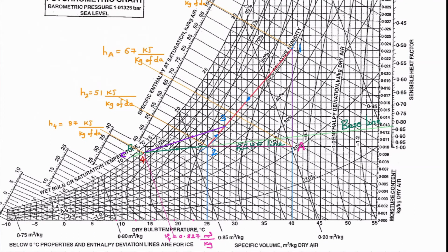Okay, now in this psychrometric chart, again this psychrometric chart, it is valid for atmospheric condition. Pressure is 1.01325 bar. Then vertical lines are dry bulb temperature lines. Inclined lines, when they cut the saturation curve, here you can read wet bulb temperature. Same line if extended on this scale, you can read specific enthalpy. Right side horizontal, we have moisture content. It is also called humidity ratio. It is also called specific humidity omega. These are relative humidity curves, 10%, 20%, and last one is saturation curve where relative humidity is 100%.